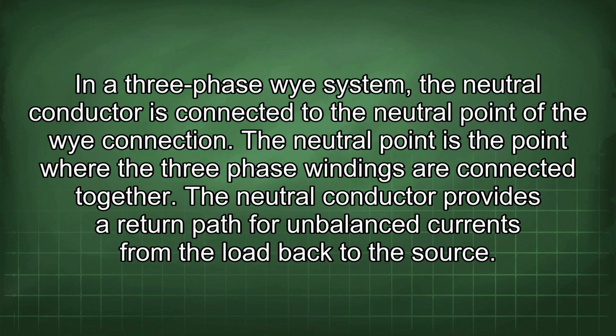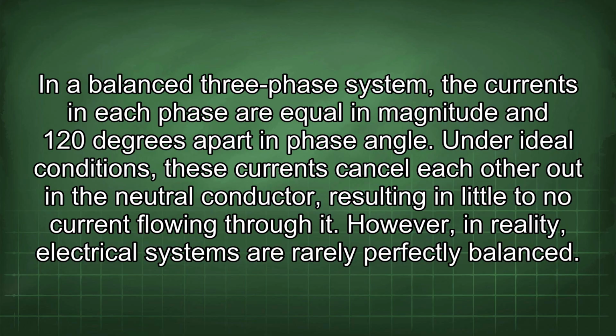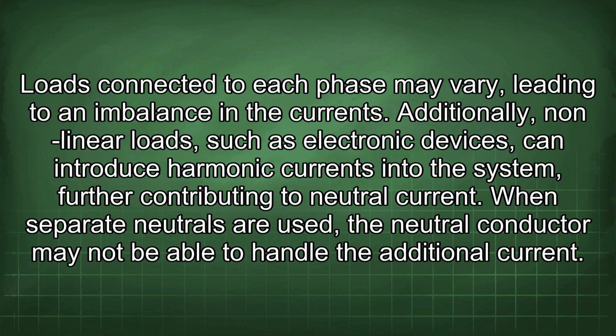In a three-phase Y system, the neutral conductor is connected to the neutral point of the Y connection. The neutral point is the point where the three-phase windings are connected together. The neutral conductor provides a return path for unbalanced currents from the load back to the source. In a balanced three-phase system, the currents in each phase are equal in magnitude and 120 degrees apart in phase angle. Under ideal conditions, these currents cancel each other out in the neutral conductor, resulting in little to no current flowing through it. However, in reality, electrical systems are rarely perfectly balanced. Loads connected to each phase may vary, leading to an imbalance in the currents. Additionally, nonlinear loads such as electronic devices can introduce harmonic currents into the system, further contributing to neutral current.